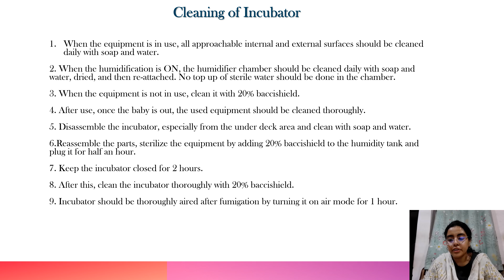Specific notes to be kept in mind are that spirit and other organic solvents must not be used to clean the incubator hood or panel. The sleeves of the access window must be cleaned daily, even if the baby is in. Always position the incubator in such a way that free air enters the air inlet. Place the incubator where there is no direct sunlight. Check and dust the air filter every day, which is present over the back area of the incubator.